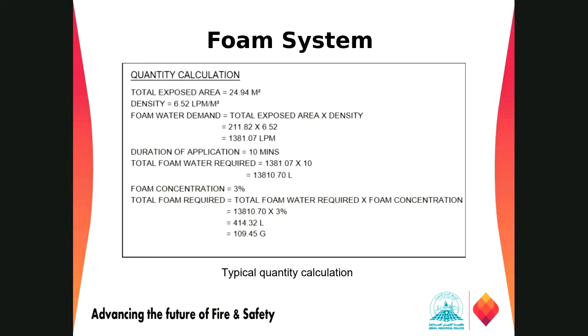As per NFPA 16, they need it for 10 minutes. So multiplying the total foam demand by 10 minutes, we have around 13,810 liters of foam water required for 10 minutes for this application. Now moving on to the foam concentration, we have 3%, so just multiply by 3%. So we need foam concentrate of around 110 gallons or 414 liters for this application.